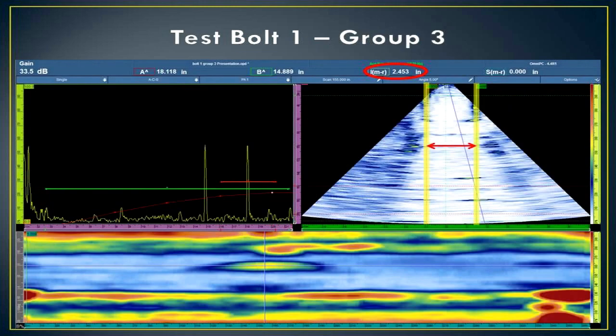So this is a scan for test bolt 1 using group 3. You can see I put the cursors over here on the thread indications up at the top, and the width between those cursors was measured 2.45 inches. That's very close to the minor diameter of the threads, which is 2.45 inches. So it's pretty accurate. I then moved the cursors in equal amounts to equal the theoretical diameter of the bolt. And now those cursors represent the body of the bolt, or approximate it.